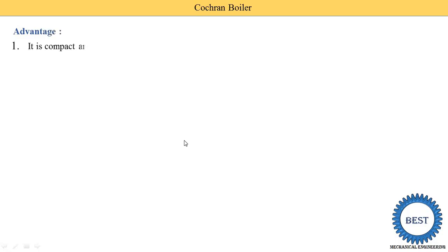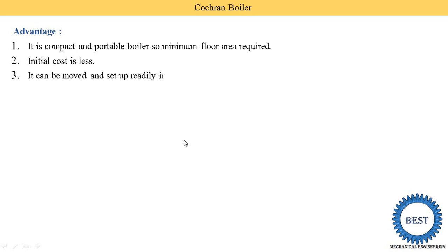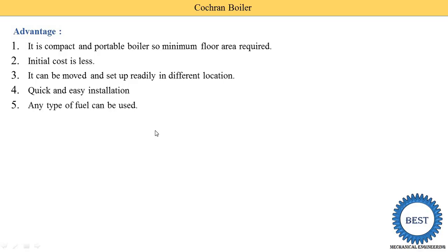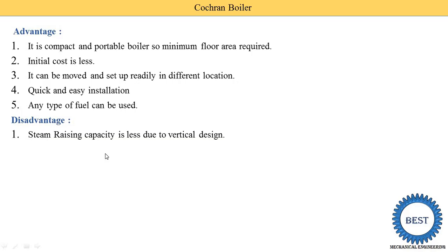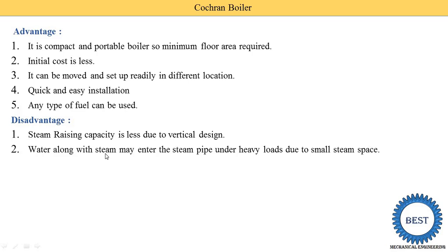The advantages of the Cochrane Boiler are: it is compact and portable, requiring minimum floor area; initial cost is less; it can be moved and set up easily in different locations; and any type of fuel can be used for combustion. The disadvantages are: steam rising capacity is less due to the vertical design, meaning lower steam is produced; water along with steam may enter the steam pipe under heavy loads due to small steam space; and efficiency is poor in smaller sizes.